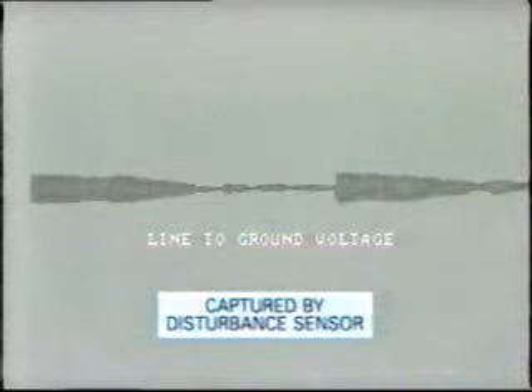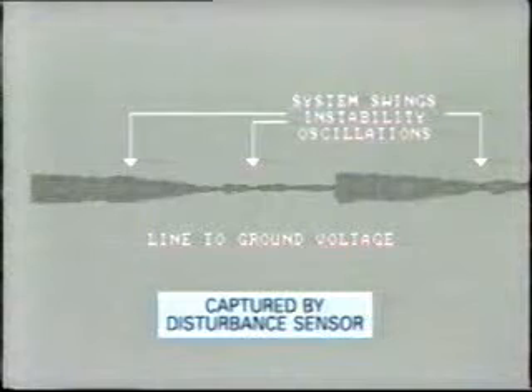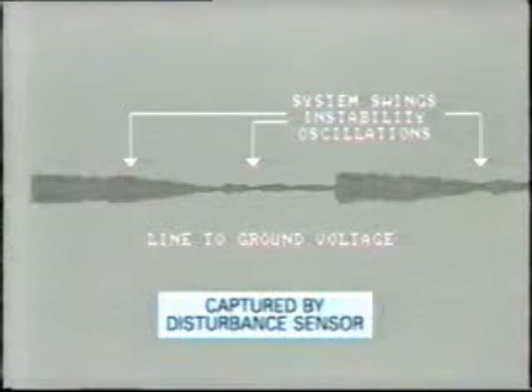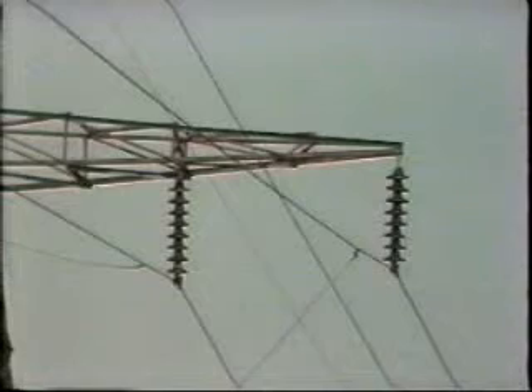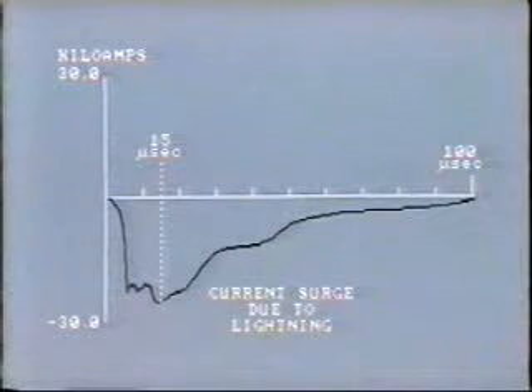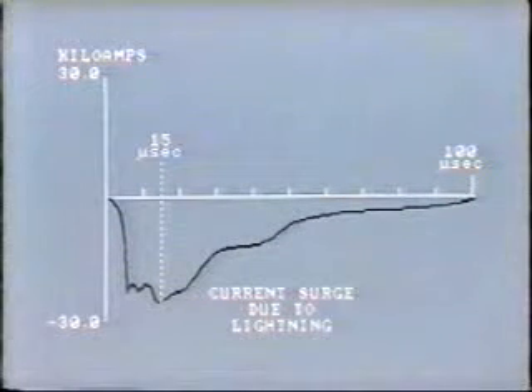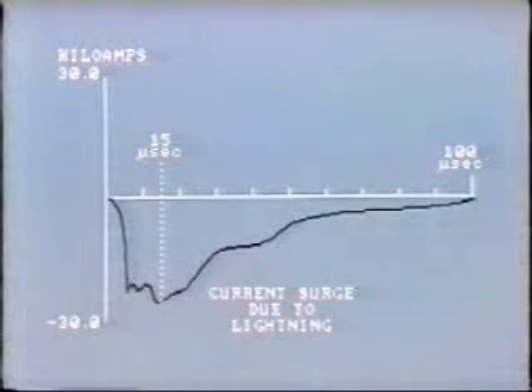Another type of sensor, the disturbance sensor, responds to slower changes in voltage, current, or even system frequency. These slower changes take place over many cycles and are commonly called system swings, instability, or oscillations. Oscillographs do have their limitations. For example, a lightning surge would not be recorded because it's much too fast. A typical current surge due to a lightning strike reaches its peak and decays to zero in a matter of microseconds. Although our conventional recording machines could not pick up the actual surge, we may be able to see the effect of the lightning.